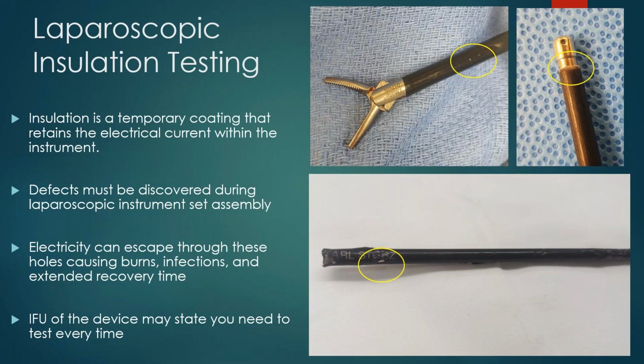But again, we're going to go through a handful of what's out in the market. Electricity can escape through these holes, causing burns, infections, and an extended recovery time. And really, the smaller the leak, the worse the burn, because it basically concentrates on that stray. If you think about it, it's almost like a water hose. If you were to take that water hose and kink it or cover it with your thumb, that's how it would be. So just because it's a smaller nick or little pinhole, it doesn't mean it's not going to do much. It's actually going to be worse than something like a gash.